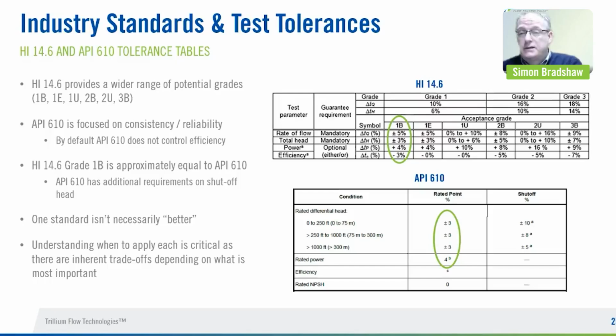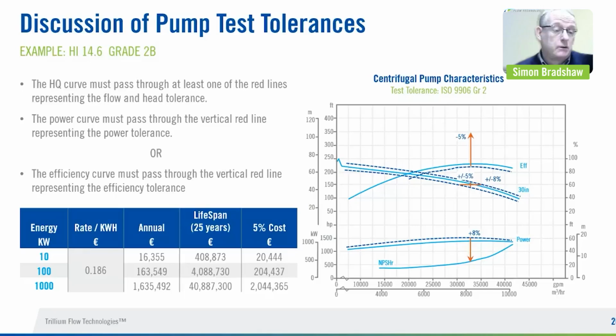The second takeaway is that over the years, the standards have tried to align. HI 14.6 grade 1B is notionally equivalent to API 610. However, API 610 has additional requirements for controlling shutoff head, which 14.6 does not have. One standard is not necessarily better than the other. It really depends on your end goals and what you're trying to achieve, as we'll see a little bit later. But there's trade-offs in using either of these standards. So let's go on to the next one.